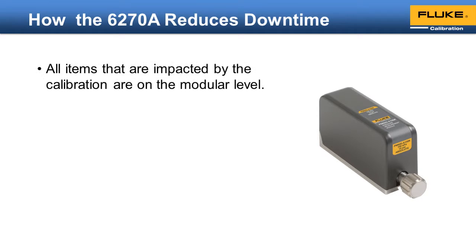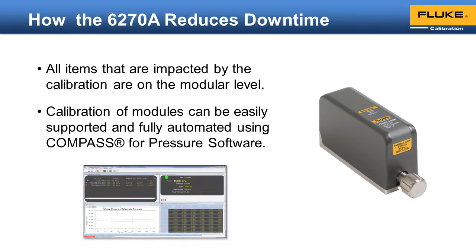Great care has been taken to ensure that all items impacted by the calibration are at the modular level. The measurement module includes the actual pressure sensing element, the electronics that read the output of the sensing element, and the coefficients that are applied to that output to calculate the final pressure value. All external influences that can affect the output of the pressure sensor — including temperature, supply voltage, and EMC — were taken into account in the design to ensure that it performs the same whether installed in a 6270A chassis or being calibrated using the optional calibration kit.